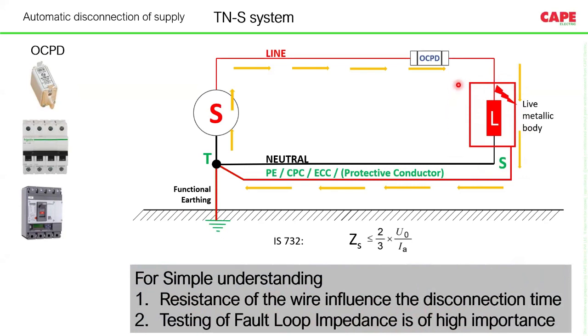Now I am moving the cursor to the location, live metallic body. It is connected to the neutral of the transformer through a metallic connection, a metallic conductor. So the exposed conductive parts or the extraneous conductive parts are finally connected to the neutral of the transformer through a metallic connection, and this metallic protective conductor must run along with the phase and the neutral conductor. Don't try to route it through a different route. So there are some rules which have to be followed here.